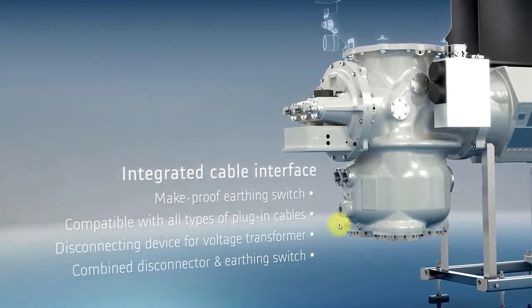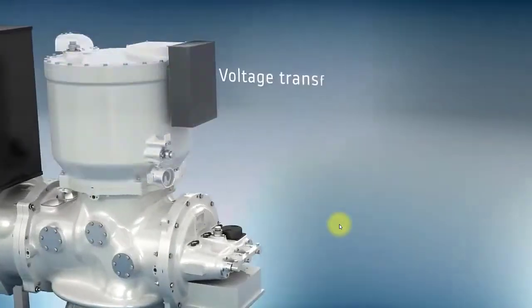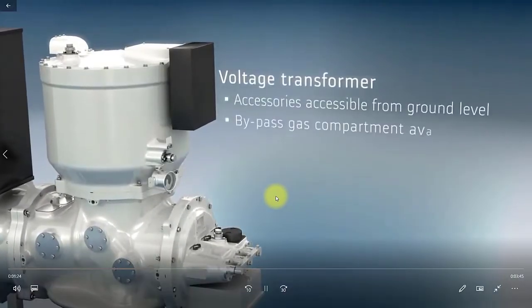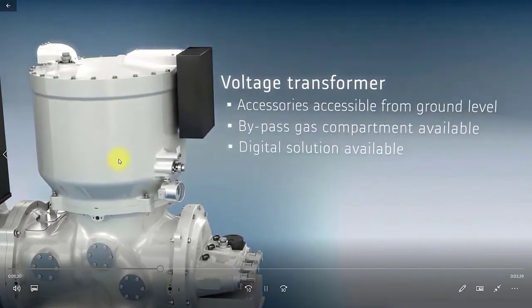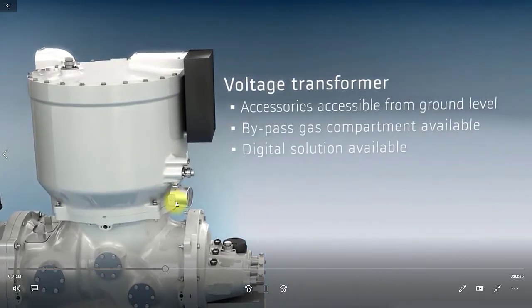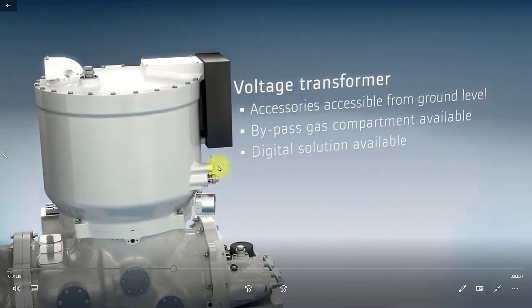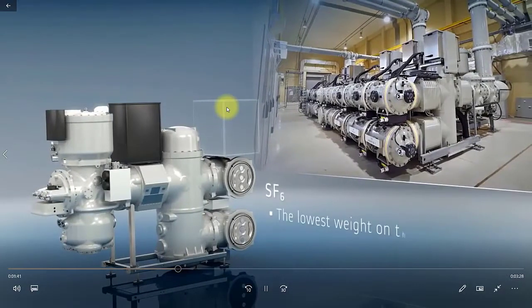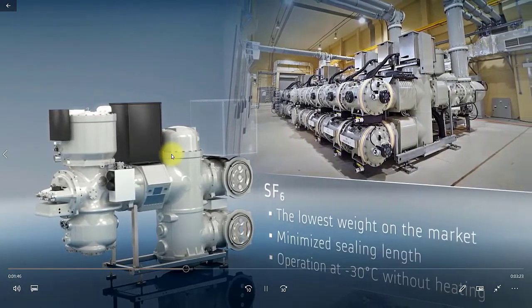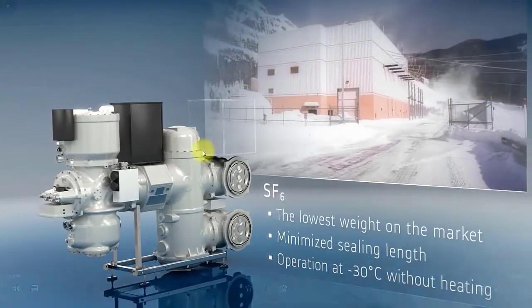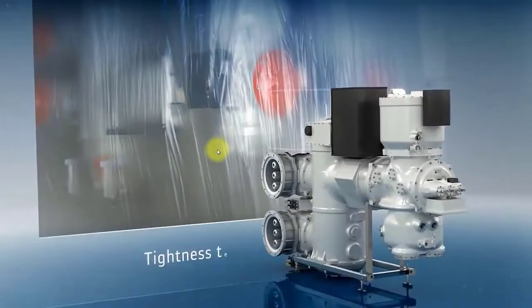This is a combined unit — the line earth switch, which is a high-speed earth switch. Here is the voltage transformer. This pressure gauge is really easily accessible. This is the gas filling point for SF6, and this is the density box. SF6 is used in this gas insulated switchgear and can operate at minus 30 degrees centigrade without heating — that is one of its key characteristics.